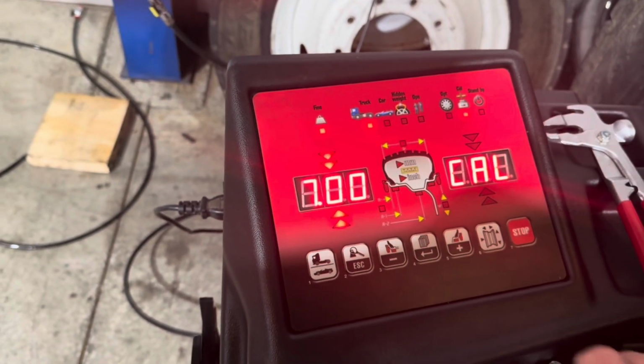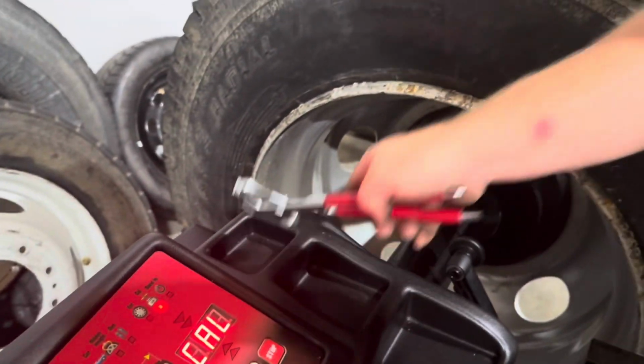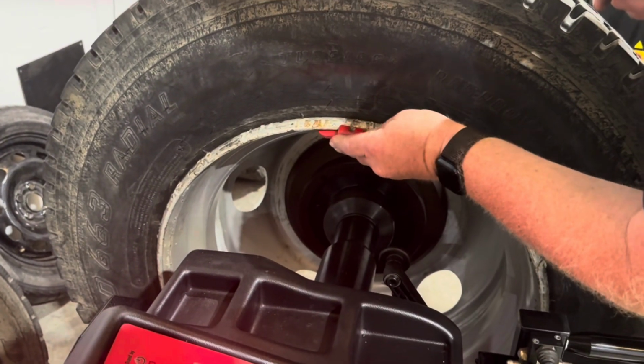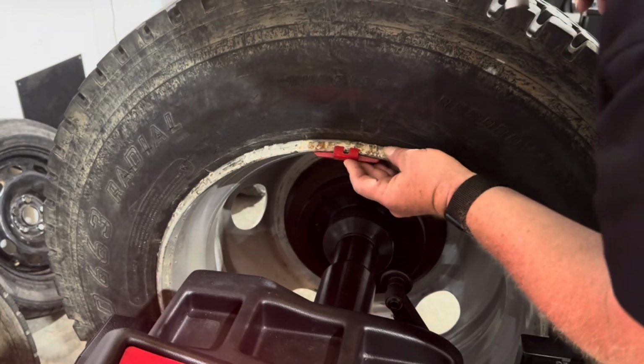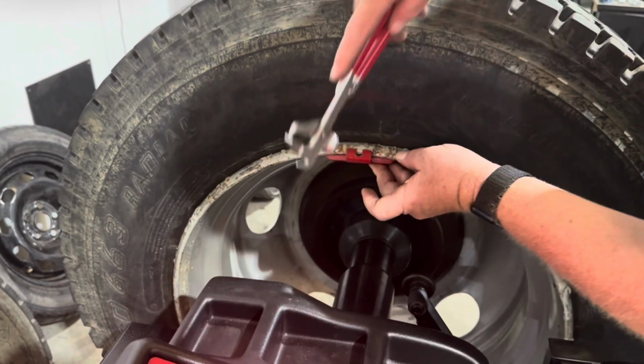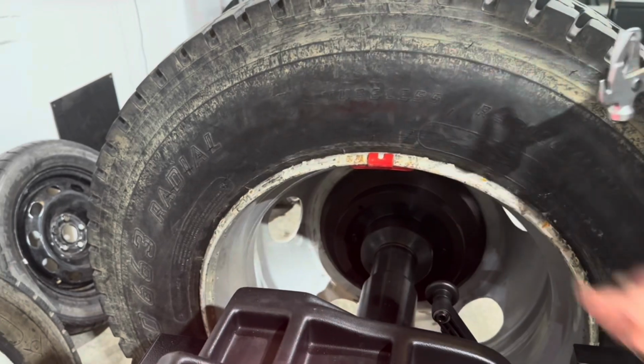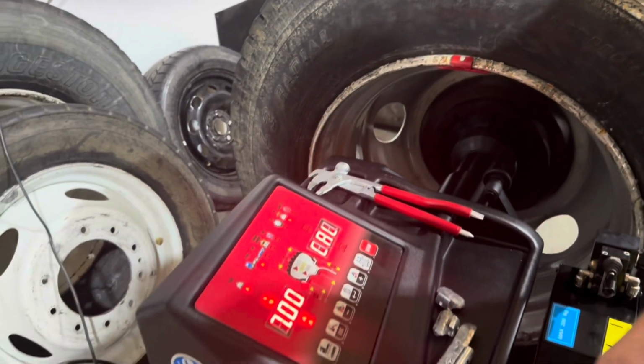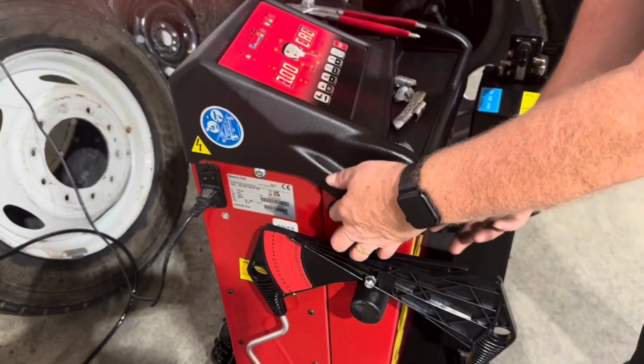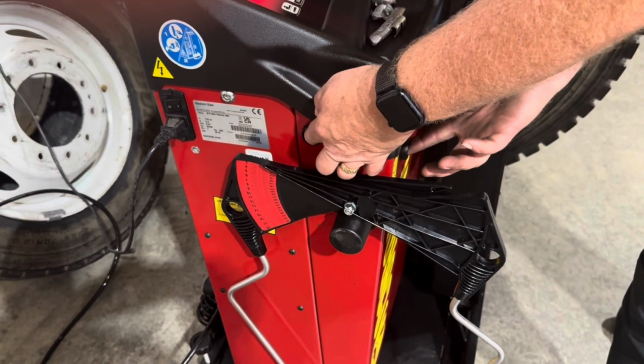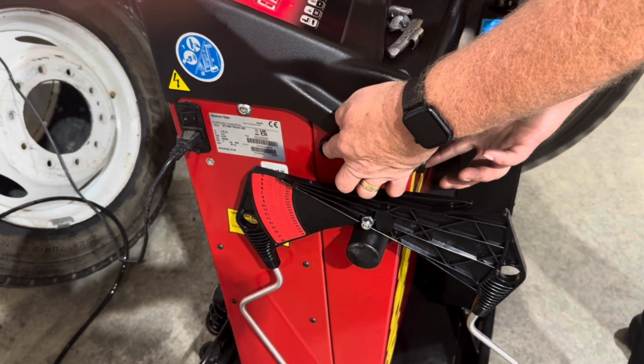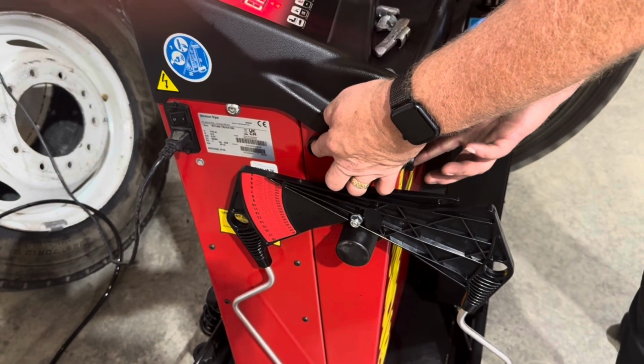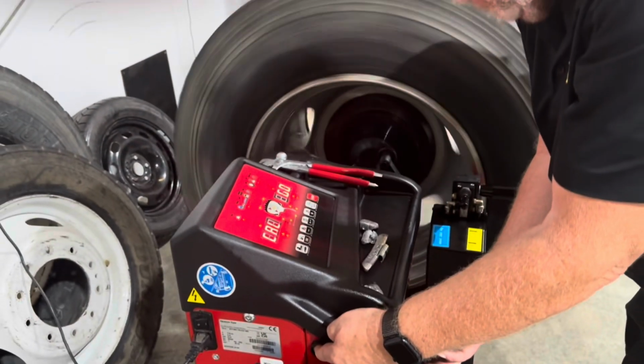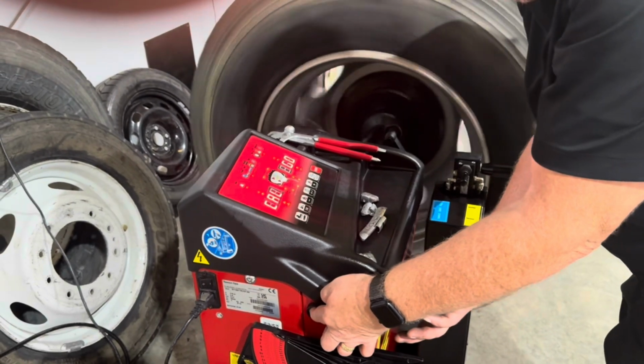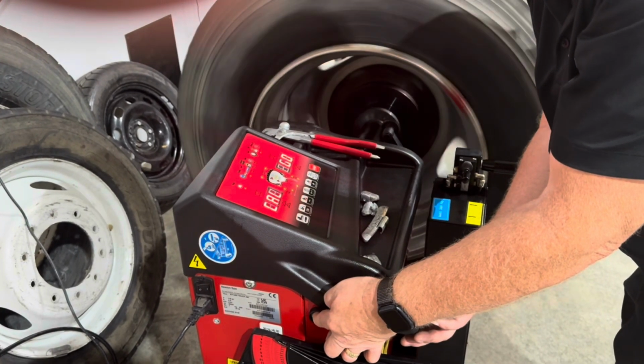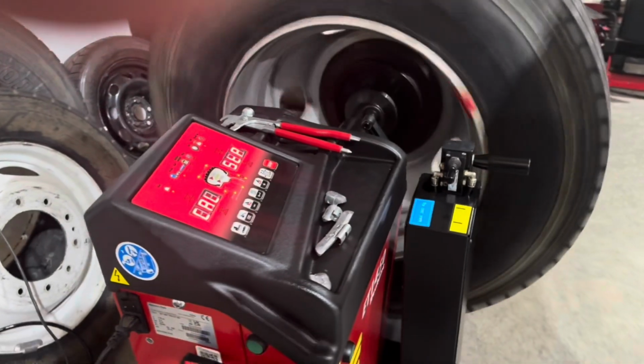Once you have that highlighted, we're going to take our 7-ounce calibration weight. We're going to put it directly at 12 o'clock, making sure that you're centered over the shaft. I'm going to hold my button on the left, and then I'm going to push and hold the 2 buttons together, the one in the front, and I'm going to hold it until I get a beep. Then I release both buttons at the same time.